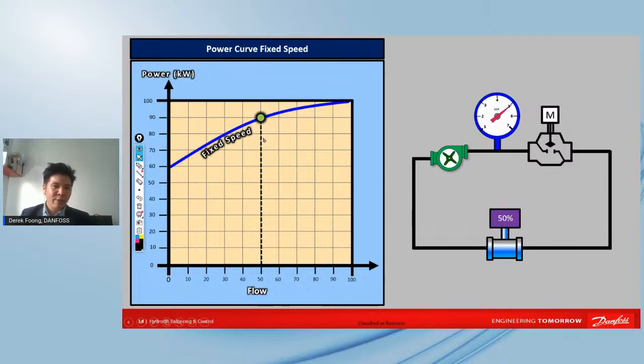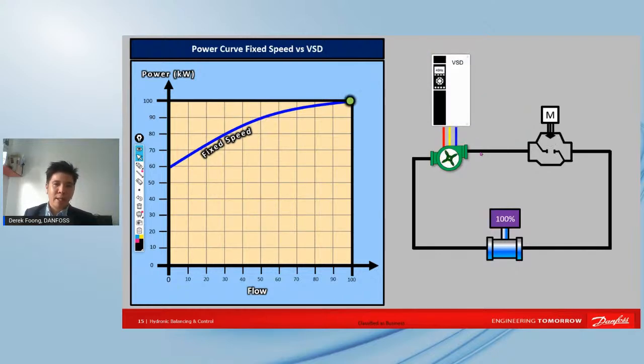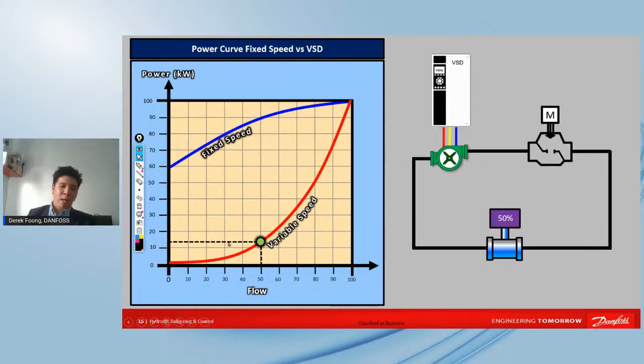So let's do a quick charting. So 50% of the flow rate would still attribute to 90 kilowatt, which is 90% of the energy consumption. So even if we don't have inverters, by reducing 50% of the flow conventionally with a control valve in a single loop, it will only reduce about 10% of the energy. But if we have a drive integrated to the pump, then of course, if we reduce the flow rate while keeping the control valve fully open, or we don't even need a control valve in this case to regulate the flow, regulating to about 50% with the cube law savings, then it will be at this point. So this is about saving about 85% of the energy while reducing about 50% flow. So this is just a very quick comparison in just a single chart.